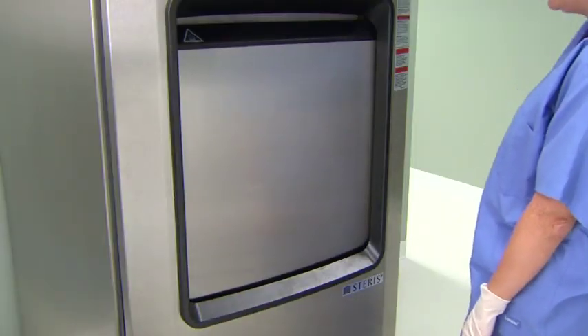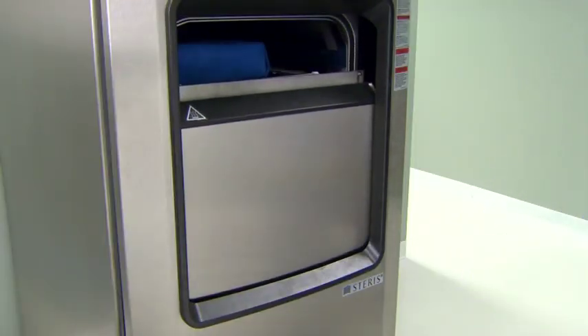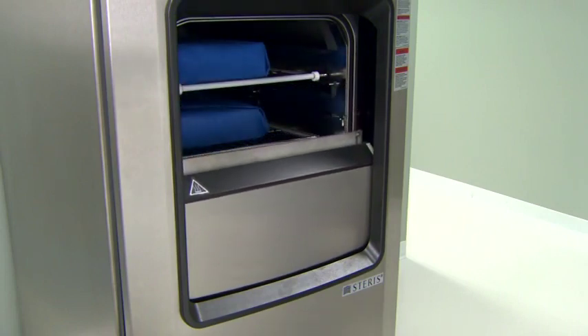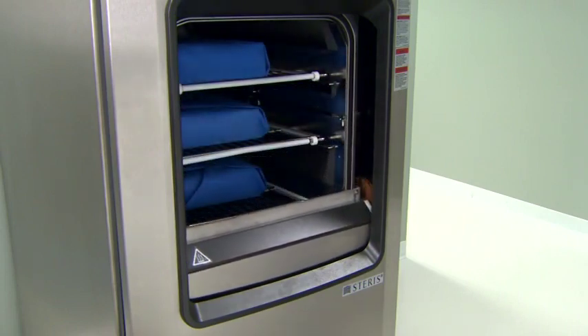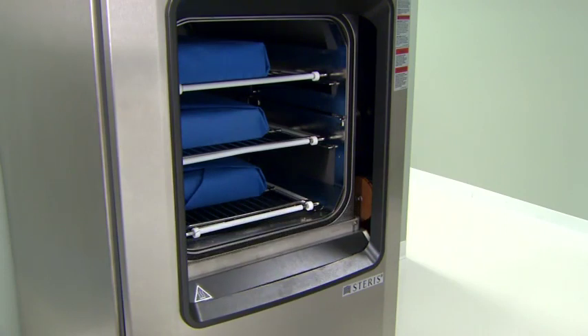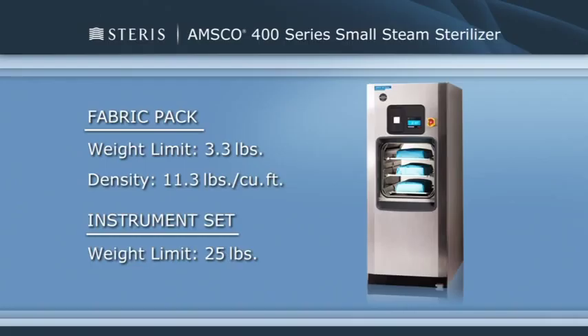The AMSCO 400 series sterilizer holds commonly used wrapped or unwrapped instruments and equipment. Wrappers must be made of 100% cotton, 140 thread count 2-ply fabric, and must be laundered. It also handles non-woven disposable wrappers. Limit the weight of each fabric pack to approximately 3.3 pounds and density to 11.3 pounds per cubic foot. This ensures complete steam penetration and minimizes moisture retention. Limit the weight of each wrapped instrument set to 25 pounds to minimize moisture retention.